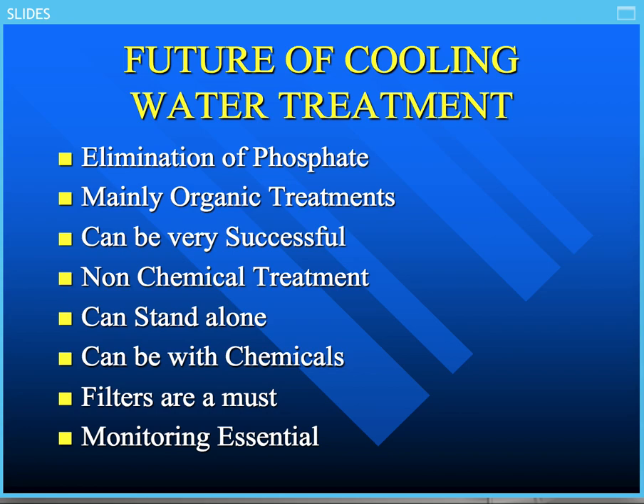There are two sponsors that we have today that have filters. Absolutely every cooling tower system in the country should have a filter, because that really is reducing your fouling problem and reducing your corrosion problem. It's reducing scaling, and it could reduce your chemical treatment cost by as much as 10 to 15%. So, to me, a non-chemical or physical treatment program, a filter, is essential.